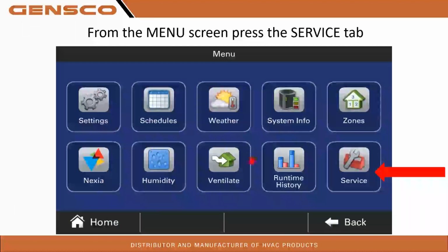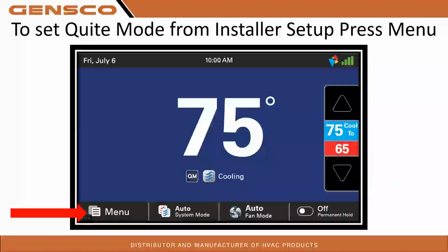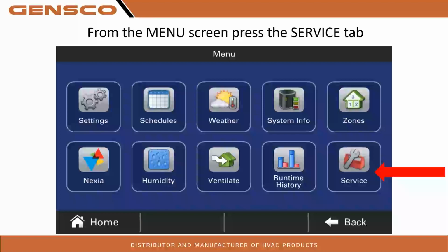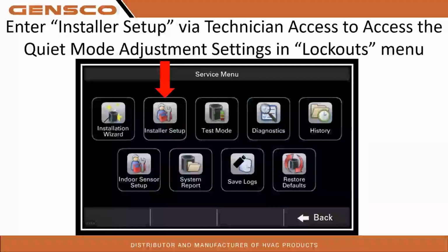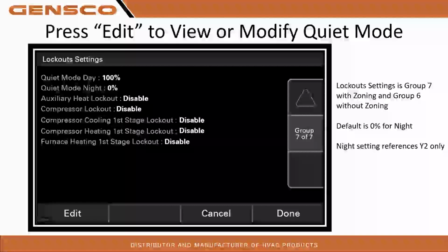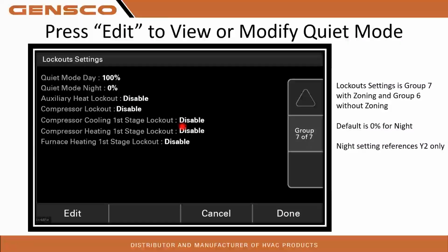Here's how we set quiet mode from installer setup. Press menu, press your service. We're going to go into installer setup. You're going to go to lockout settings, group 7 of 7. You can see that that's factory default. It comes at 0%.